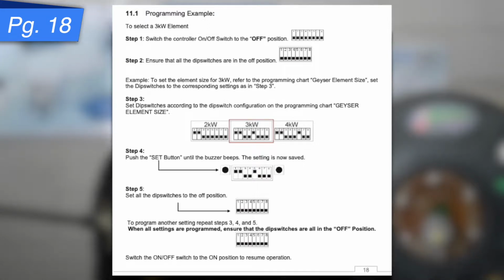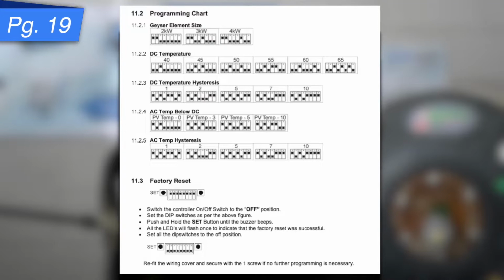And then of course, once you've made all those changes in the dip switches, you can switch the toggle back on and switch the geyser controller on as well. So that's how you make changes to the controller using the dip switches. On page 19, you'll see the dip switch settings for the various settings that you may want: the geyser element size, the DC temp, the DC temp hysteresis, the AC temp below DC, which we recommend, if you remember, was 10 degrees less preferably, and the AC temp hysteresis. And how to restore factory settings is indicated on page 19, 11.3.